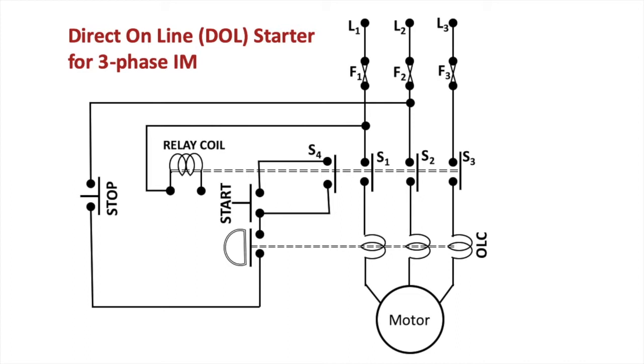So that is the protection of the motor through the relay coil. It basically functions as a no-volt relay: if there is no supply voltage across this relay coil, it will be de-energized and it will open the supply connected to the motor. The stop button is normally in the closed position, and if we want to stop the motor, we press the stop button, so this contact is opened. As soon as the stop button is opened, the supply to the relay coil is disconnected and the switches S1, S2, S3 will be opened. So this is how the DOL starter works for a given motor.